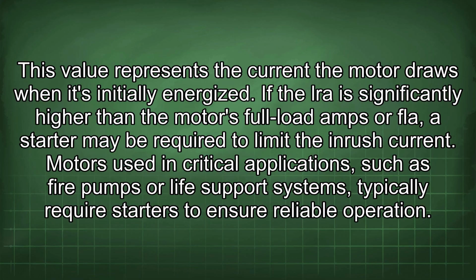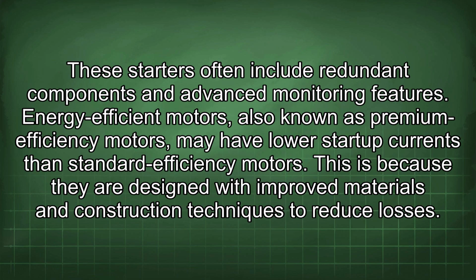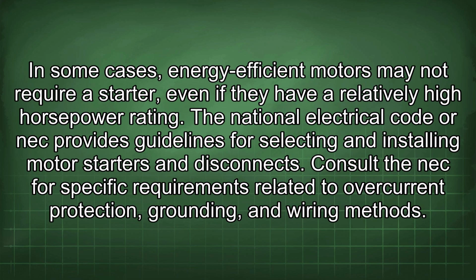to ensure reliable operation. These starters often include redundant components and advanced monitoring features. Energy-efficient motors, also known as premium efficiency motors, may have lower startup currents than standard efficiency motors. This is because they are designed with improved materials and construction techniques to reduce losses. In some cases, energy-efficient motors may not require a starter, even if they have a relatively high horsepower rating.